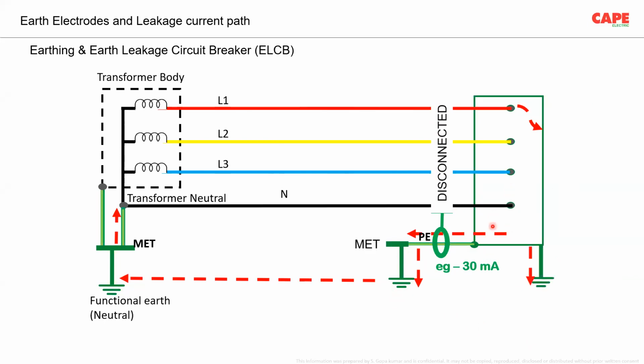For example, imagine in your installation, you have made a wrong connection, meaning for one of the equipment you took one more earth wire and connected it to another part of your installation, probably somewhere else. If a leakage current flows through an alternate path, we are in trouble, because we are disturbing the disconnection mechanism of the ELCB. As a result, we don't know whether during leakage the ELCB will trip or not. So making this kind of mistake, the second connection which I am showing on the pointer, is a problem.